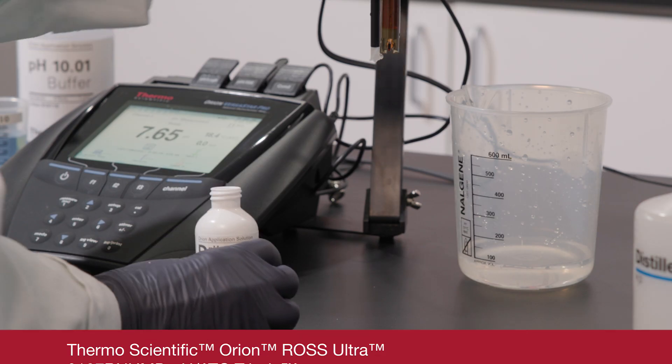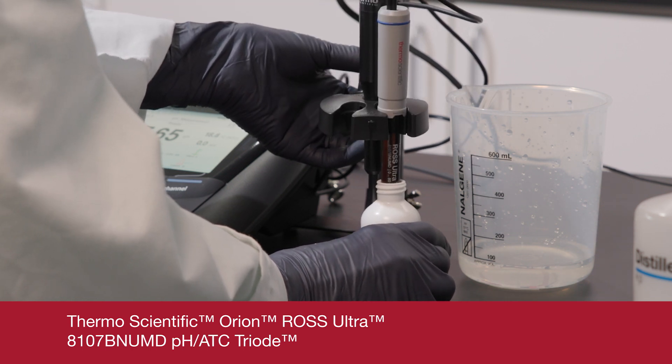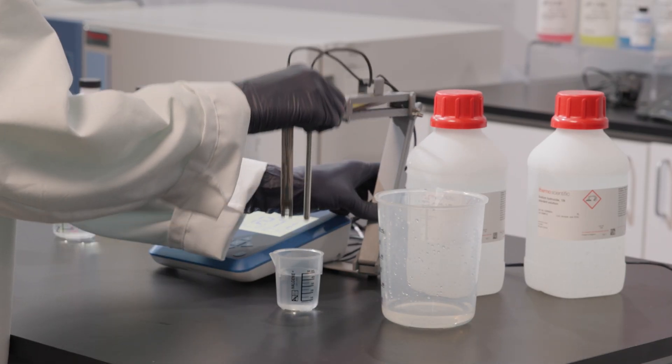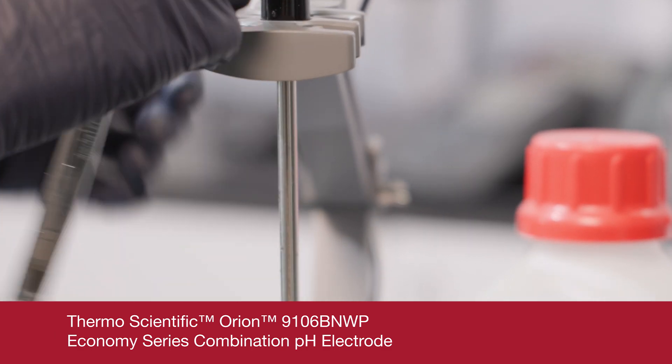Maintenance is an important design consideration as well. While all electrodes require cleaning, non-refillable gel-filled electrodes tend to require less maintenance than refillable electrodes. For aggressive samples, a basic gel-filled and low-maintenance electrode is a suitable option that can be disposed of when it stops working.